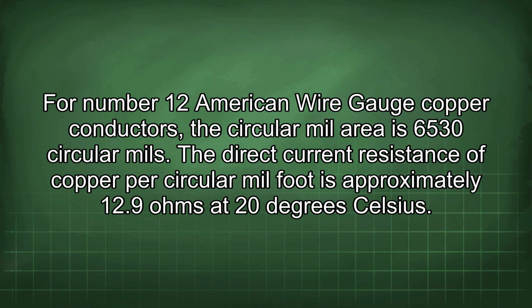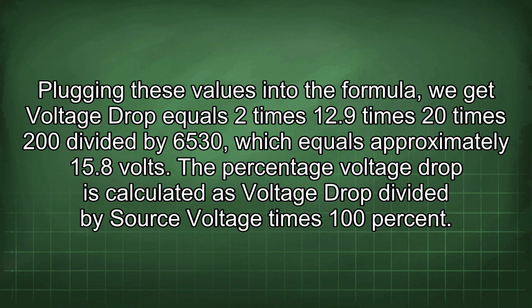For number 12 American wire gauge copper conductors, the circular mil area is 6,530 circular mils. The direct current resistance of copper per circular mil-foot is approximately 12.9 ohms at 20 degrees Celsius. Plugging these values into the formula, we get voltage drop equals 2 times 12.9 times 20 times 200 divided by 6,530, which equals approximately 15.8 volts.